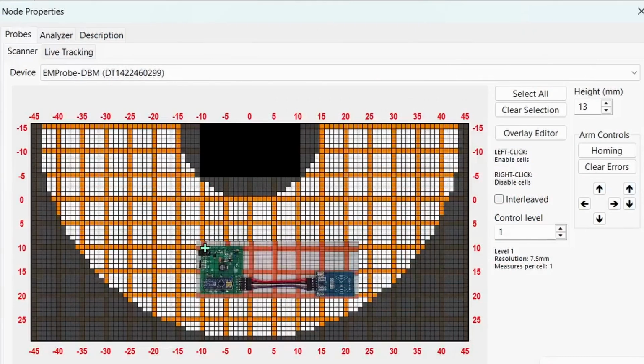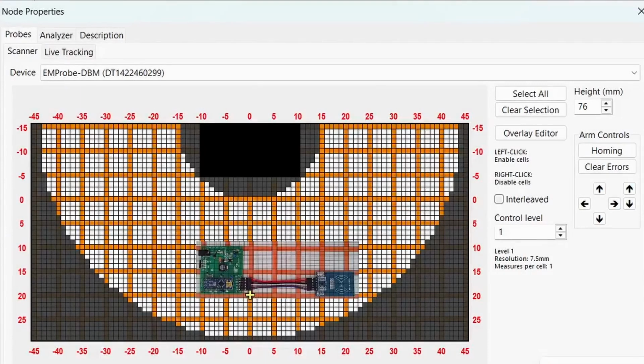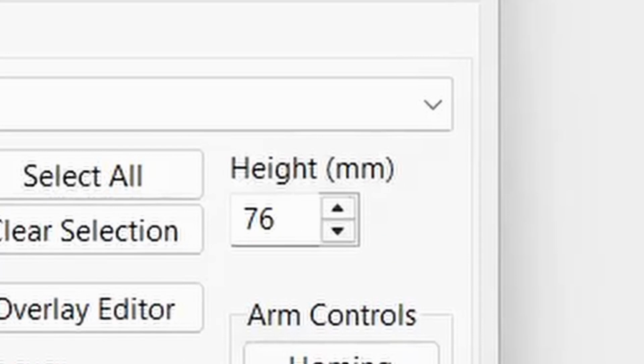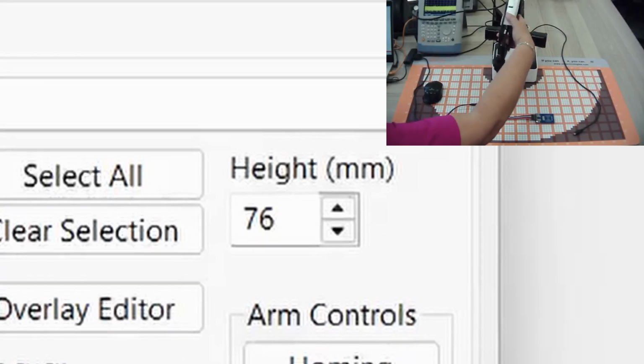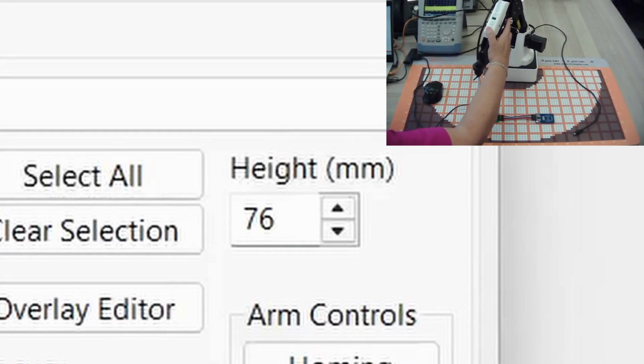Let's select the area we would like to scan. Unlike the EM scanner, the robotic arm can scan at different heights, which can be selected across the scanning area. This can allow you to follow the DUT topology accurately, especially if you have protruding components. The height we are selecting at is determined by the height control on the top right of the window. Moving the arm using the unlock button or the software arrows will update the control with the arm's current height.